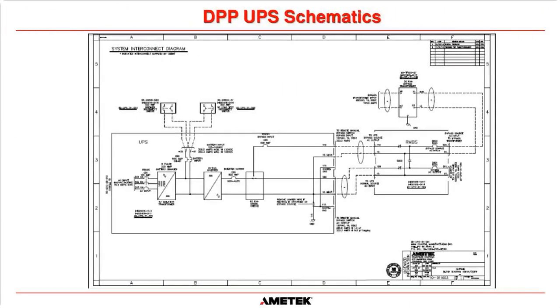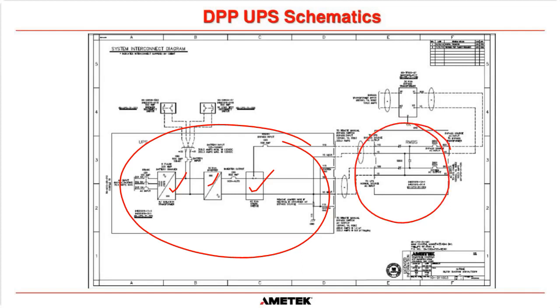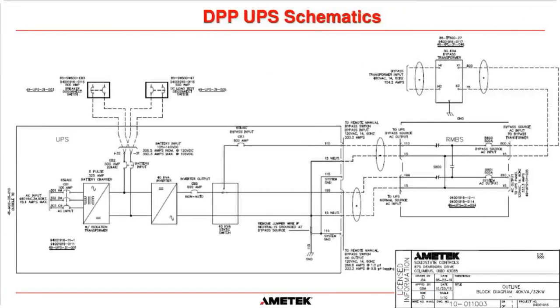So what I've done is I picked out a drawing where they've actually shown that connection for you. So here is a UPS: charger, inverter, static switch. Okay, and then here is our MBS, sorry. Okay, so I'm going to zoom in on it for you. As you can see, this is coming from your MCC, and then we actually supplied a bypass transformer for the customer here. So the bypass comes in here, and then it goes out into the bypass for the UPS. But the output of the UPS goes in here, out through this contact here, and out to the load.